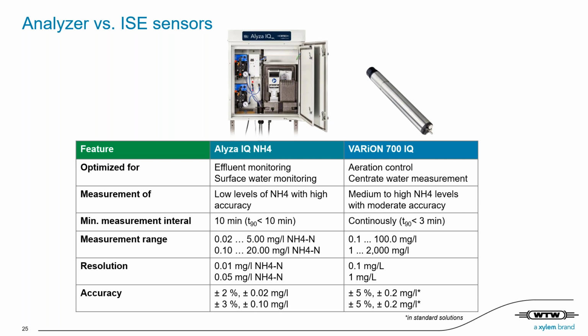For this application, in contrast to monitoring tasks where intervals between 10 minutes up to 12 hours are appropriate for measurement, a continuous measurement of ammonium is required, which can really be provided by ISE sensors with a T90 time below 3 minutes. ISE sensors are also perfectly suited for other applications where high concentrations of ammonium occur. For example, the measurement of the centrate water from sludge dewatering, where concentrations can be detected over 1,000 milligrams per liter NH4-N.